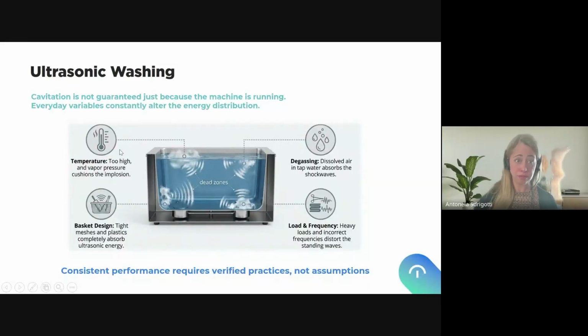So as I have mentioned, if the temperature is too high, they will provoke vapor pressure that will cushion the cavitation energy or the implosion of these microscopic bubbles that remove the organic residues, provoking dead zones. Everyone that has used an ultrasonic washer knows that we have to degas the solution. What is degasification? It is the elimination of the gases dissolved in the water. And these are the bubbles that we can actually see when we start the machine. These bubbles need to go out. These are air bubbles trapped in the water that decrease a lot the cavitation energy. So this is why we do the degasification before we put the load. We eliminate this air inside the water.